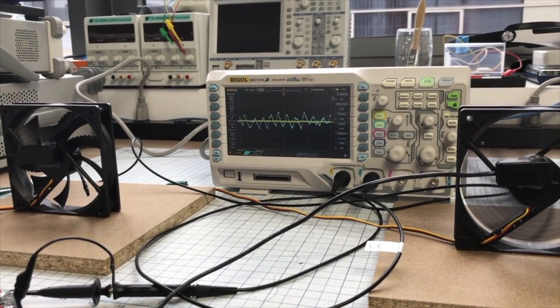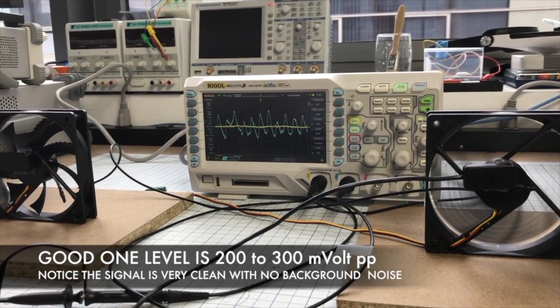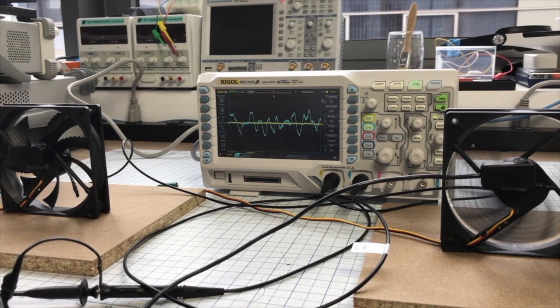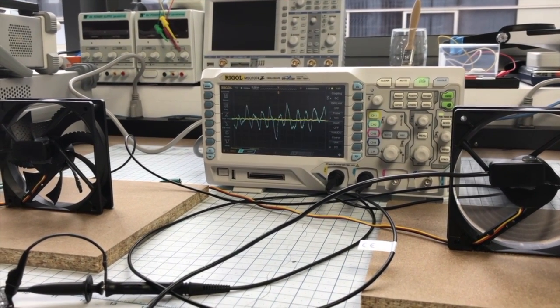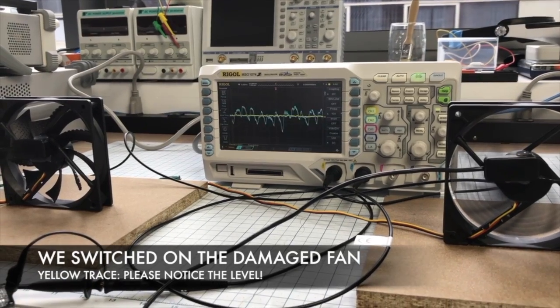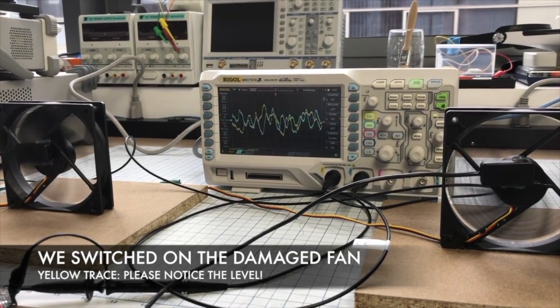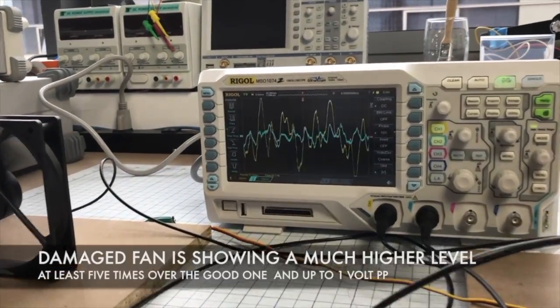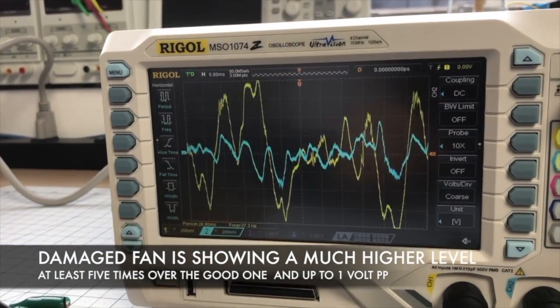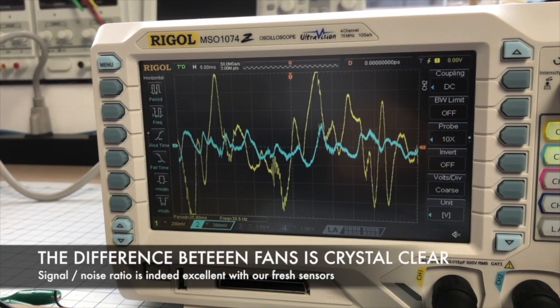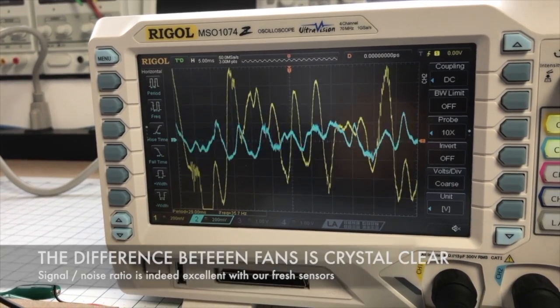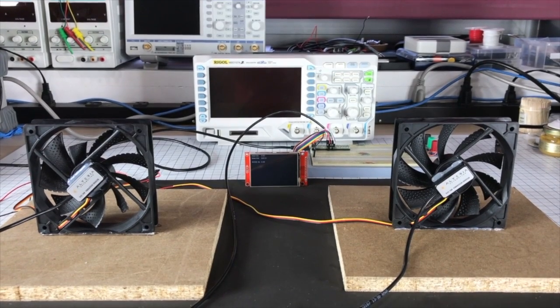the undamaged fan running. We see the vibration on the screen, and now we are switching on the damaged fan on the left, and you will see in the yellow trace on the oscilloscope that there is a huge difference in the amplitude level on both fans. That was not visible before with the accelerometer transducer.